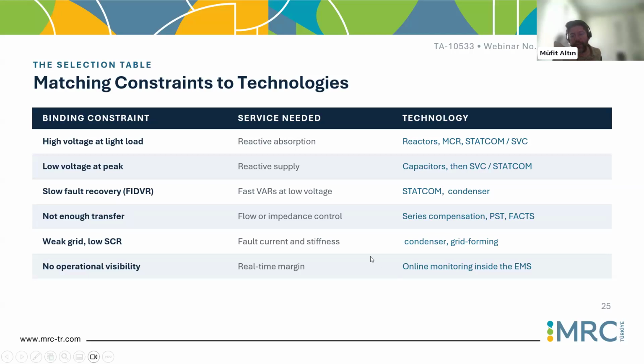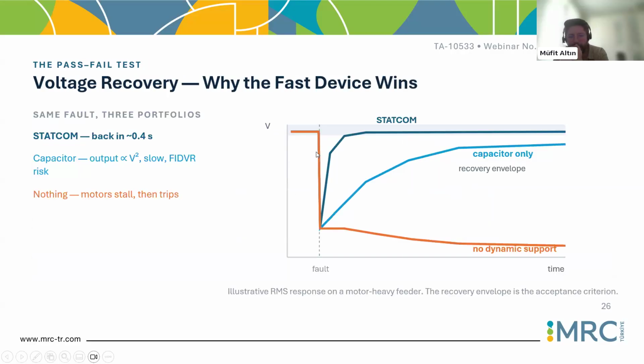No operational visibility: if you cannot see, you cannot control. The real-time margin is important in this case. Online monitoring inside the EMS or SCADA systems is becoming more important. In addition, I checked recently: there is a market for active power frequency control, but even right now not for reactive power or voltage control issues. The UK, I think, is still trying to develop such a market for reactive power and voltage control. Next slide, please.